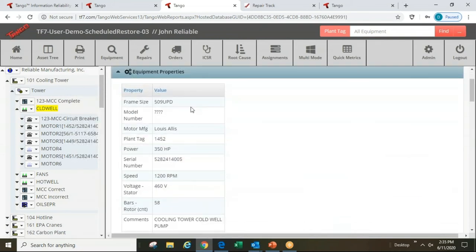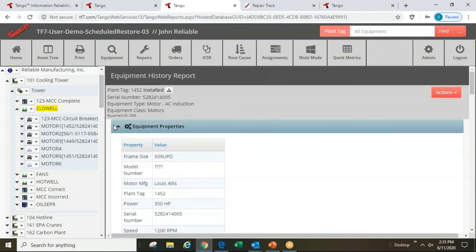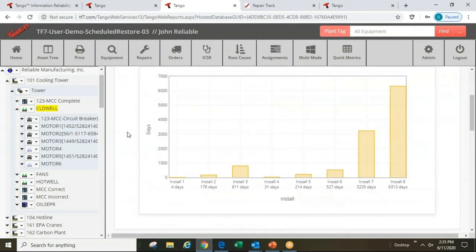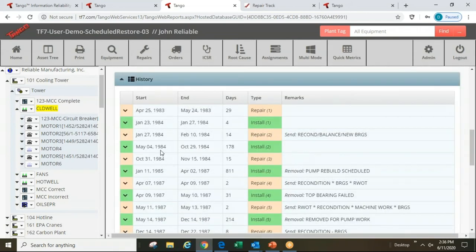Here, a particular motor — a 509UPD frame, 350 horsepower, 460 volt — designed for a cold well pump location. This is actual data from an aluminum smelting operation where an engineer was keeping his own database until the late 1990s when he realized it wouldn't survive Y2K, and imported all his info into our system. This motor had been installed six or seven different times with very short mean time between failure — a few days, half a year, two and a half years, a month, less than a year — before finally starting to improve.